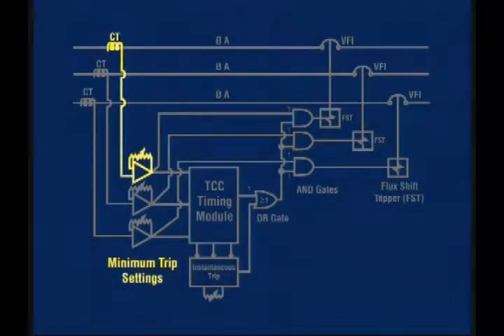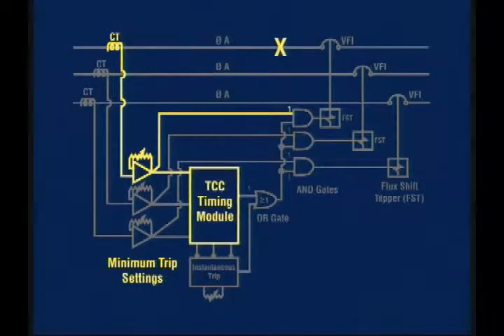The control requires no external voltage supply or battery backup because it's powered by system current through the CTs. It's not affected by system voltage conditions such as overvoltage transients. At normal system current levels, load current is continuously being compared to the programmed minimum trip values. The TCC circuit is activated whenever current exceeds the pre-selected minimum trip value. When it's activated, the TCC circuit uses the magnitude of the overcurrent to establish a time delay.